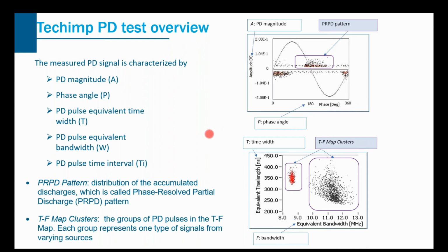And the uniqueness of Techimp technology is the TF map. The TF map uses the third and the fourth parameters to represent the acquired signals, as shown here. The idea is that PD pulses from the same source tend to have a similar shape, because it's the same source and the pulses go through the same path to reach the sensor. So the pulse shape will be quite similar. Remember, the two parameters, the time width and the bandwidth, are representative of the pulse shape.